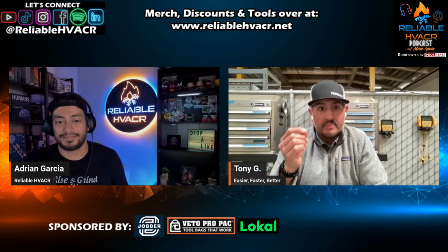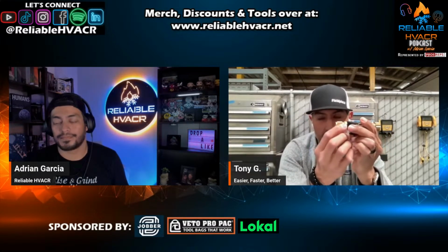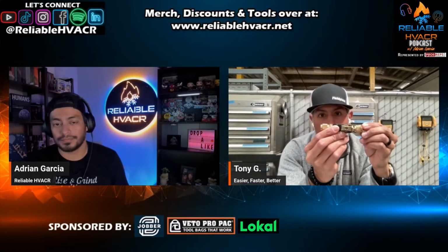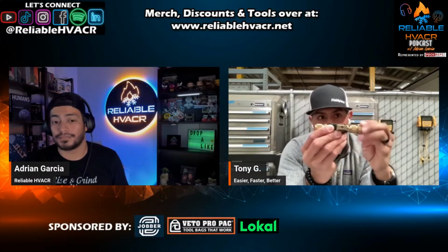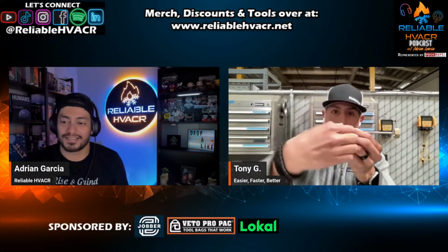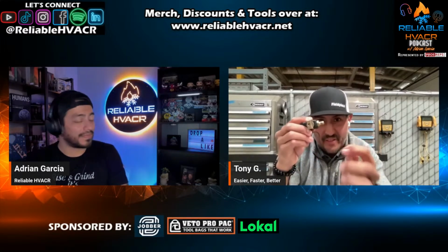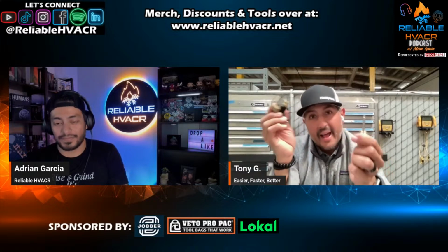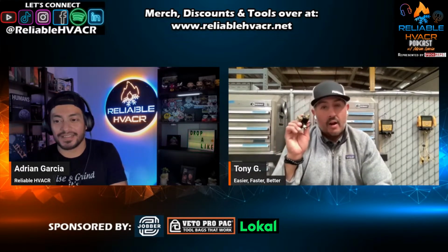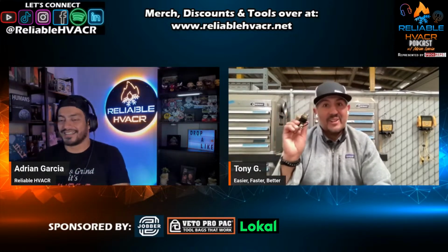Yep. And you know what I'm talking about when I'm talking about removing a valve core removal tool, right? You screw your female flare fitting onto the service port. You have your plunger, you stick it in, you grab onto the valve core, and then you're unscrewing and screwing, hoping that you unscrewed it enough. You pull out your plunger, close your ball valve, and then you take this off, and this is where you say your prayers, hoping that valve core is here at the end. And I never get it on the first try. Exactly. If someone says that they always get it on the first try, I'm going to introduce you to a liar, because none of us get it on the very first try every single time.